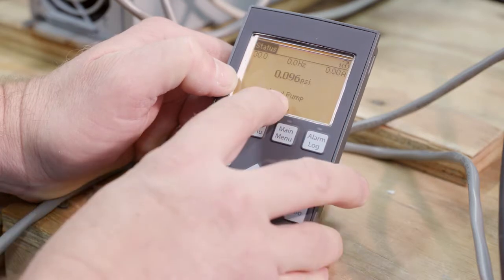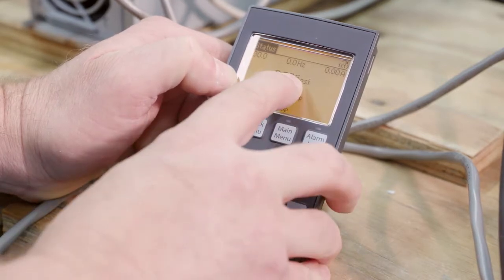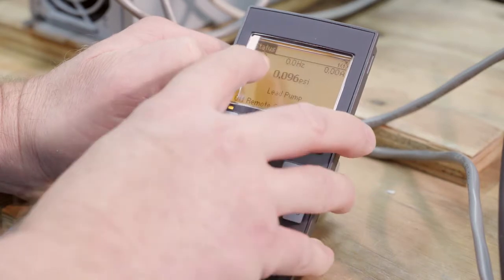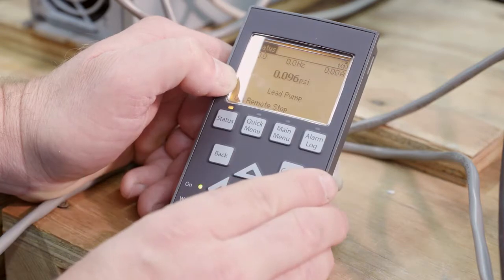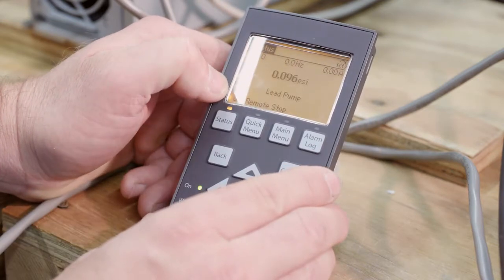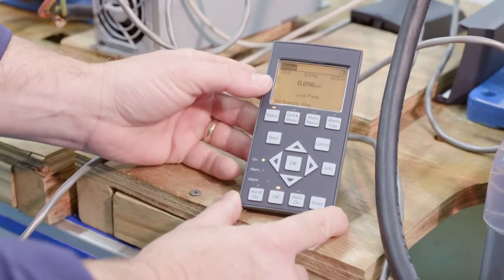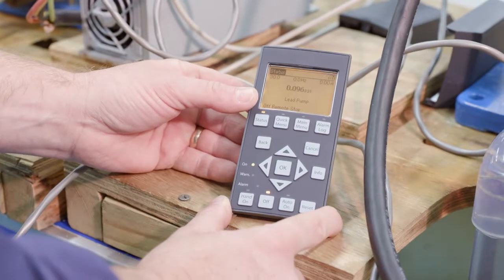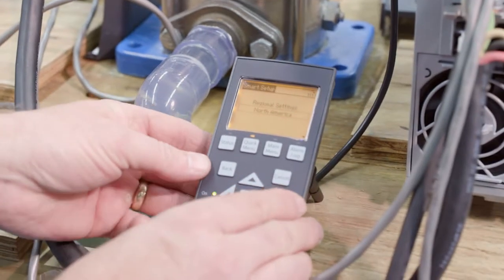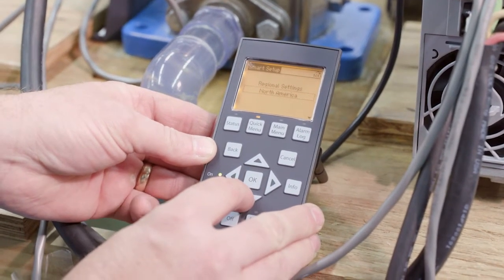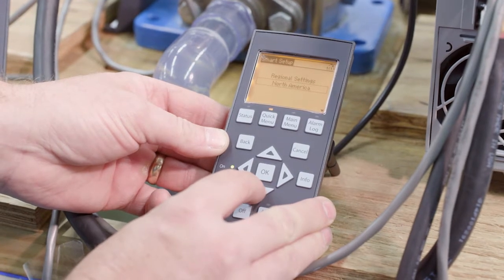All right, so we can see here I'm lead pump. All right, here's my system pressure, and it defaults here. Right, so all these are defaults, and you could change any one of these parameters on your keypad. So if you don't like the default display, you can change any one of these. So we completed the programming for what we'll call the lead pump here. And so now we need to move on to the lag pump. So again, we got to go through our settings. We're in the smart setup, we're Genie.